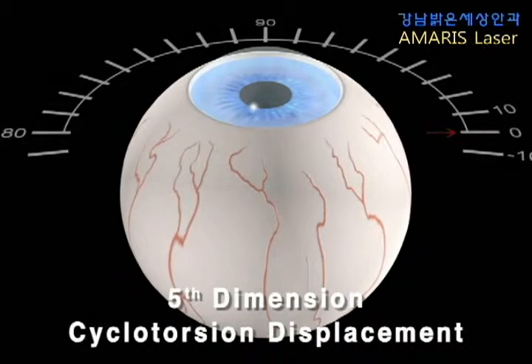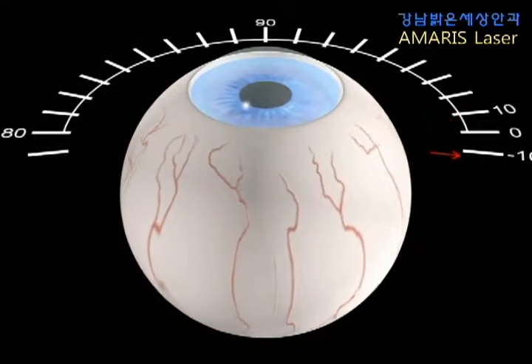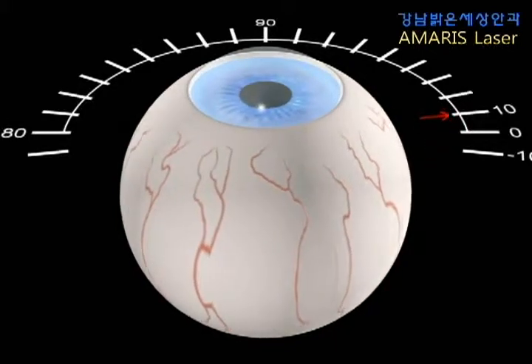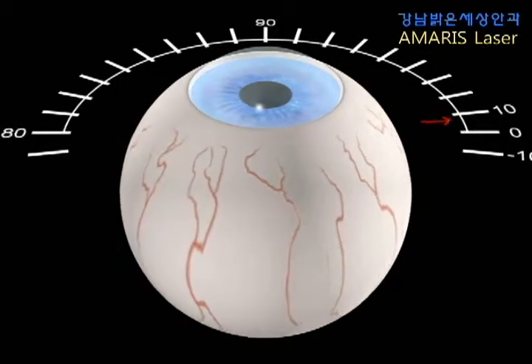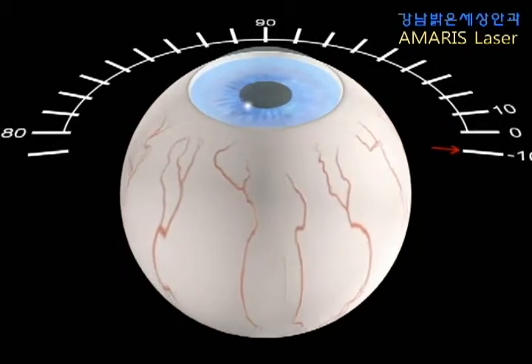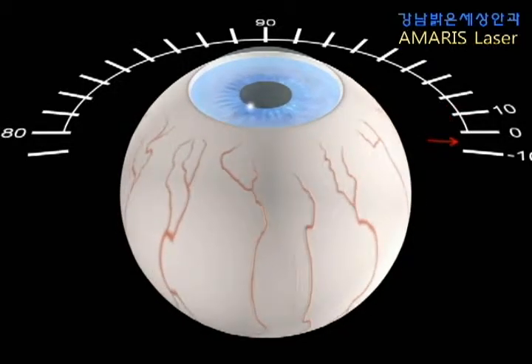The fifth dimension describes the cyclotorsion of the eye. Static and dynamic cyclotorsion control, pioneered by the SCHWIND AMARIS, compensates for torsional differences of the eye between a patient in upright and supine position, as well as torsional movements of the eye during the ablation process.